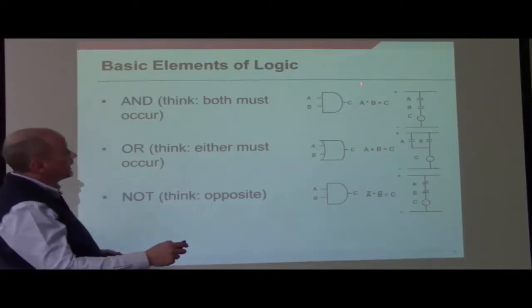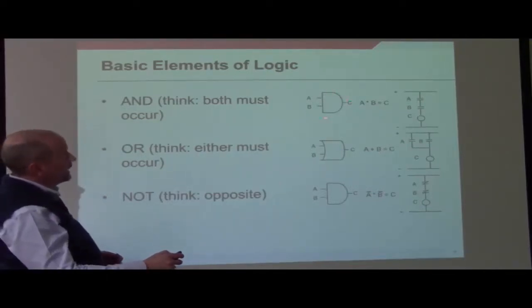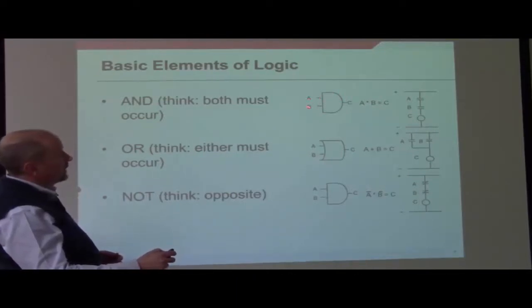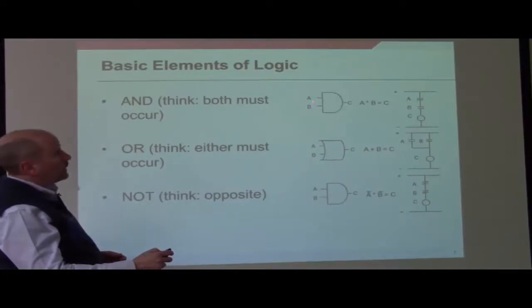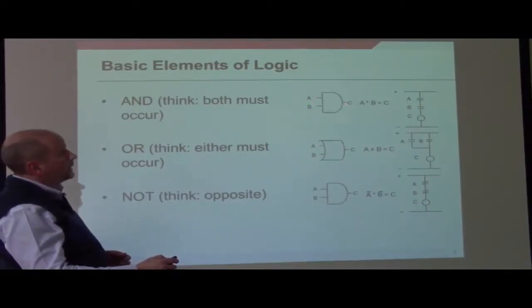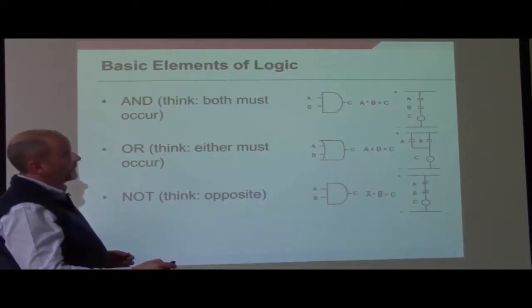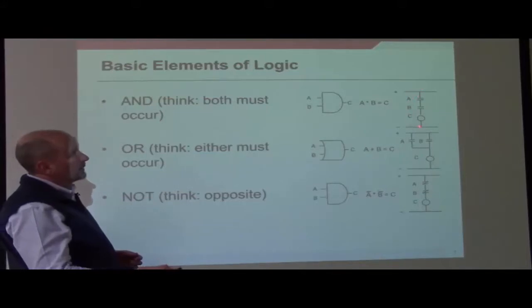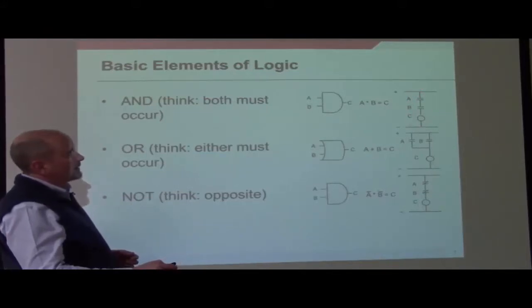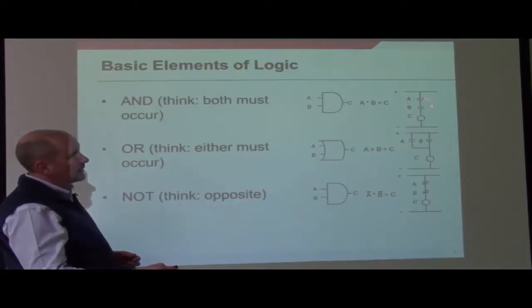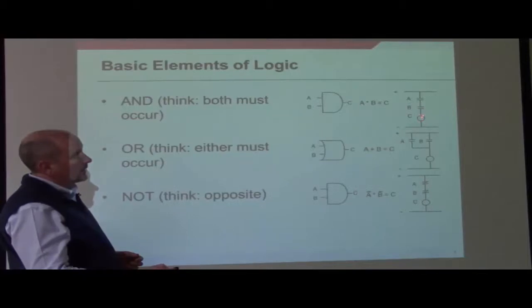The first one here is a simple AND gate, I'm sure you've seen these before. If A and B are both asserted, or value 1, then C becomes 1. This is the symbol, or the same exact logic, in a Boolean equation. And here is how we would depict it in ladder logic. This makes good sense, because if that contact is closed and that contact is closed, you will energize the coil of your relay.